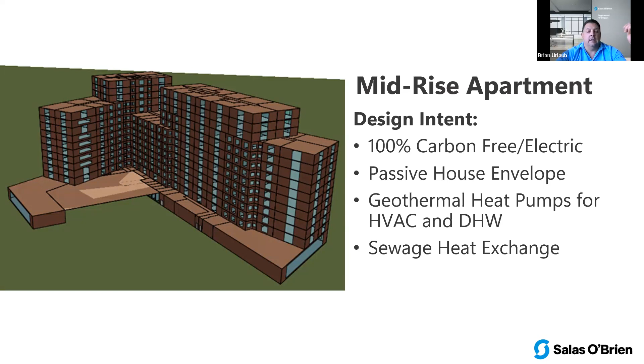And when we started looking at this, it was interesting because we were using traditional tools in the marketplace to design the geothermal ground loop. And we really just didn't feel comfortable with the results we were getting. And then we started to look at TRNSYS and go, okay, because when you add sewage heat recovery and we can use that as heat rejection, heat extraction, how does that really impact the system? And GLD or some of these other tools just don't have that capability. So then you get into a lot of manual calculations, and we needed something a little more dynamic that was hour by hour, that we could really look at, how does all this work together?